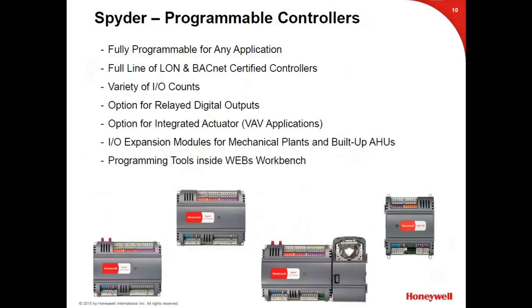Let's look at the Spyder — the fully programmable controller for any application. We have LON versions and BACnet versions with various I/O counts, including relay digital outputs versus triacs only. You can get integrated actuators — the third unit from the left has the actuator on it. You can also get I/O expansion modules. The programming tools are embedded inside our Webs Workbench. We have a DC power supply on the Spyder — if you have a humidity sensor that needs power, you can power it right off the Spyder.